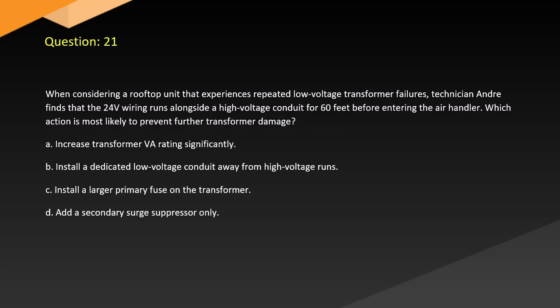Question 21. When considering a rooftop unit that experiences repeated low-voltage transformer failures, a technician finds that the 24-volt wiring runs alongside a high-voltage conduit for 60 feet before entering the air handler. Which action is most likely to prevent further transformer damage? A. Increase transformer VA rating significantly. B. Install a dedicated low-voltage conduit away from high-voltage runs. C. Install a larger primary fuse on the transformer. D. Add a secondary surge suppressor only.